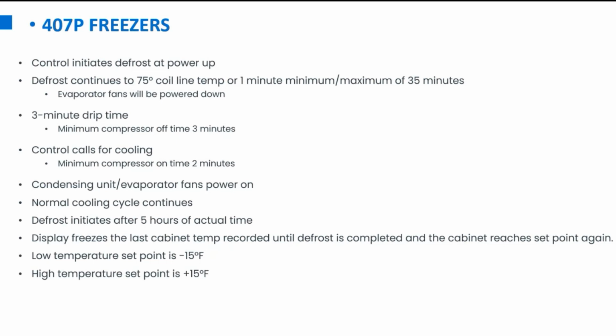The defrost on this is pretty similar to a refrigerator, but the time is a little bit different. It's going to actually initiate a defrost every 5 hours of clock time. So again, nothing based off coil temperature, nothing based off of compressor runtime, anything like that. So again, using the example, if the unit goes into a defrost around 12 noon, it's going to go into a defrost again roughly around 5 p.m. that afternoon. And then again, you'll see those different set points there.